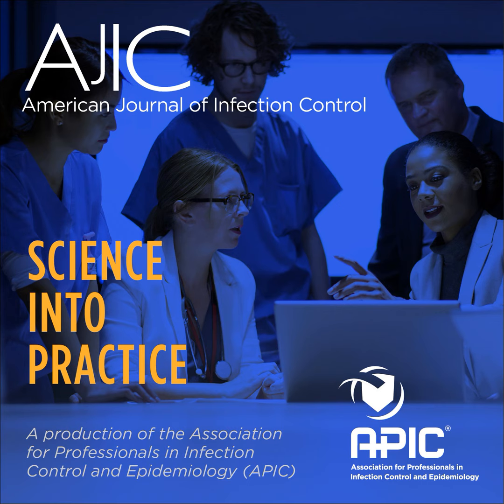Sure. Duodenoscopes are both uniquely tough to reprocess, and they're also very good at passing on pathogens if that reprocessing isn't done correctly. Like any endoscope, duodenoscopes have long working channels or tubes that you use to get the tools down to the end of the scope. Cleaning and drying these channels is like a much harder version of trying to clean and dry the straw and innards of your kid's water bottle before it grows mold. Duodenoscopes are unique in the endoscope world due to their elevator mechanisms, which provide plenty of nooks and crannies for bioburden and pathogens to hide in.